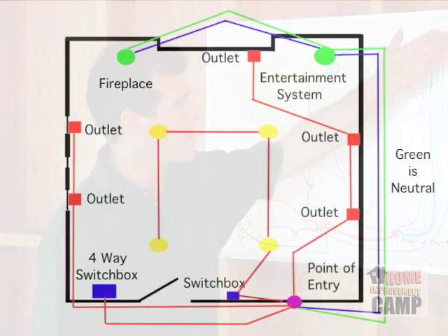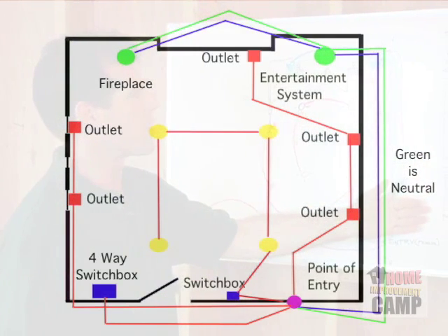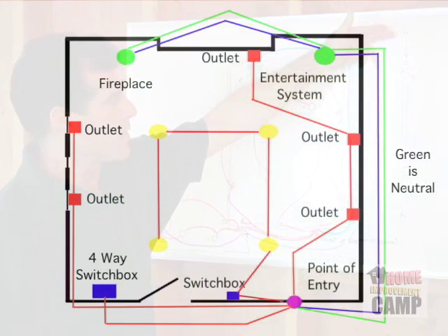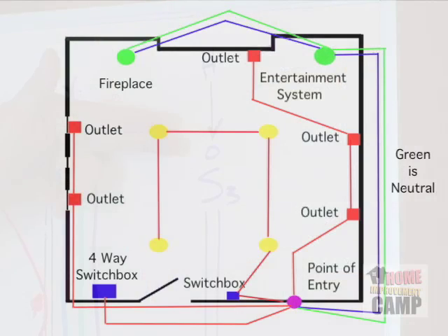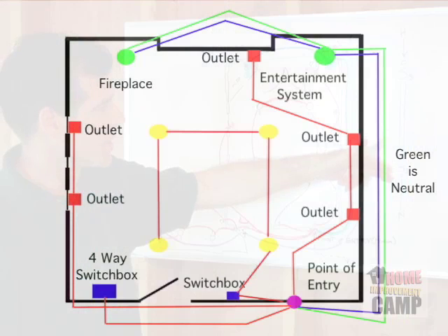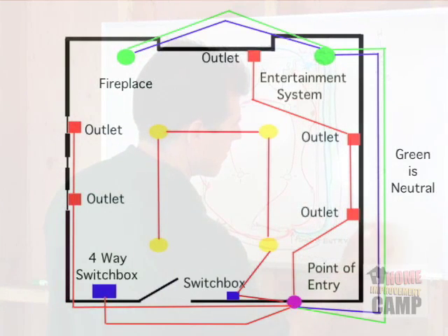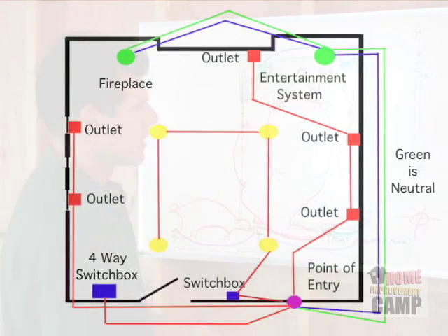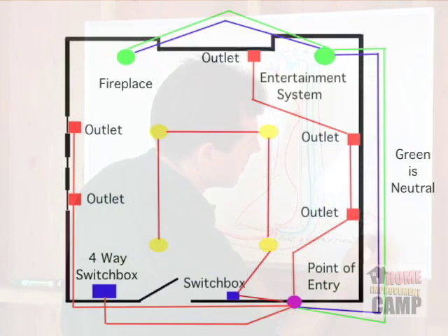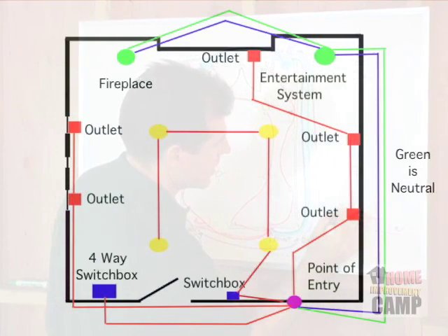I've got a drawing that shows how it works. The hot goes into the three-way switch. The traveler legs go out of the three-way switch to the second three-way switch, and the hot comes out of the three-way switch going to your light. Your light will have your neutral, and coming off your switch will be hot.